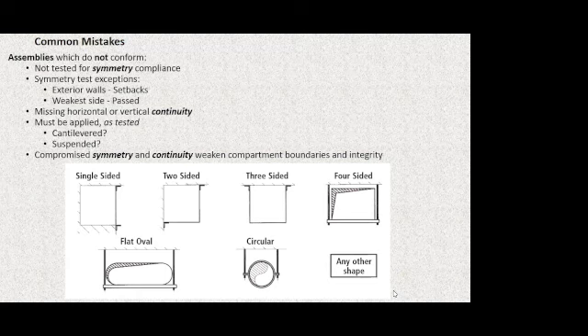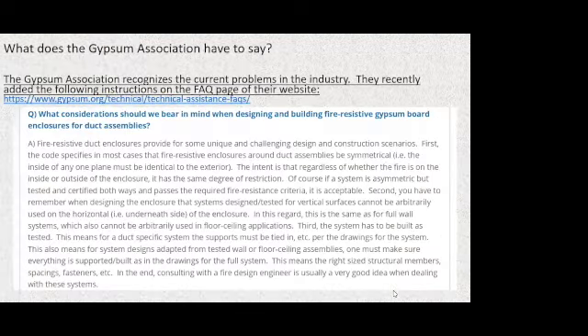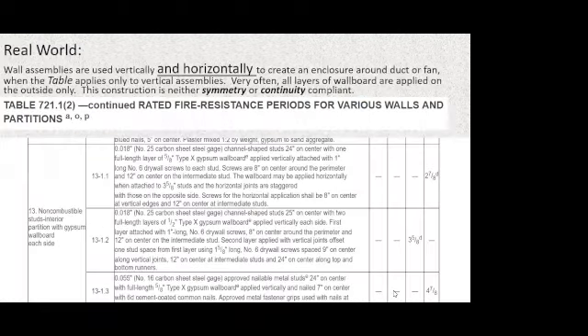We need to eliminate those that are in the wrong orientation. They have no continuity to their design. They have not supported correctly for the orientation. And we need to use them the way that they were tested. If it was cantilevered, we need to make sure it's cantilevered and supported on at least one side. Is it suspended? There's no such thing in drywall land. If it's a duct system, it's going to be suspended, and we need to very carefully, because of that, follow the hanging system requirements. Remember, there is no gripple wire and strap in fire duct land. If you don't believe these things that I tell you, I encourage you to go to the Gypsum Association's frequently asked questions, and you're going to see that they say the same thing.